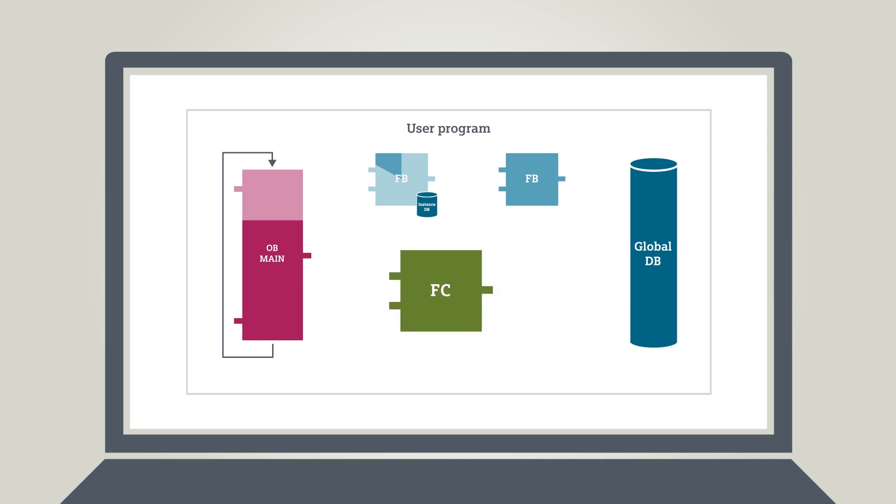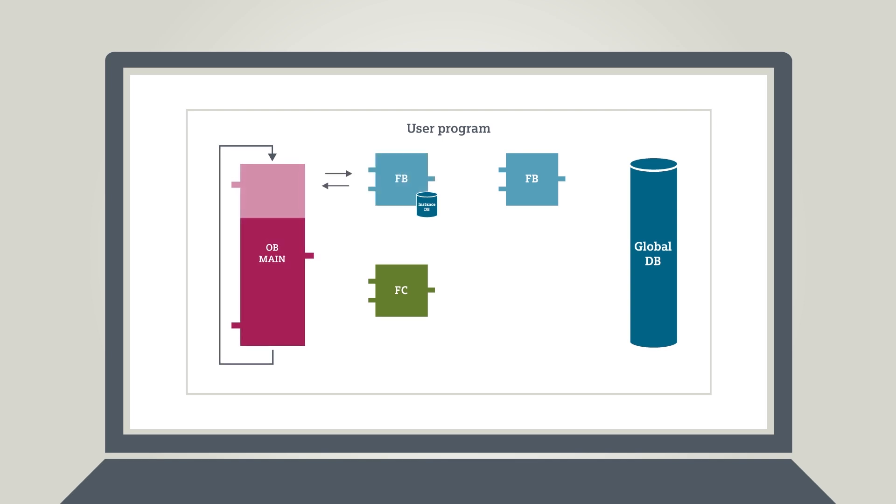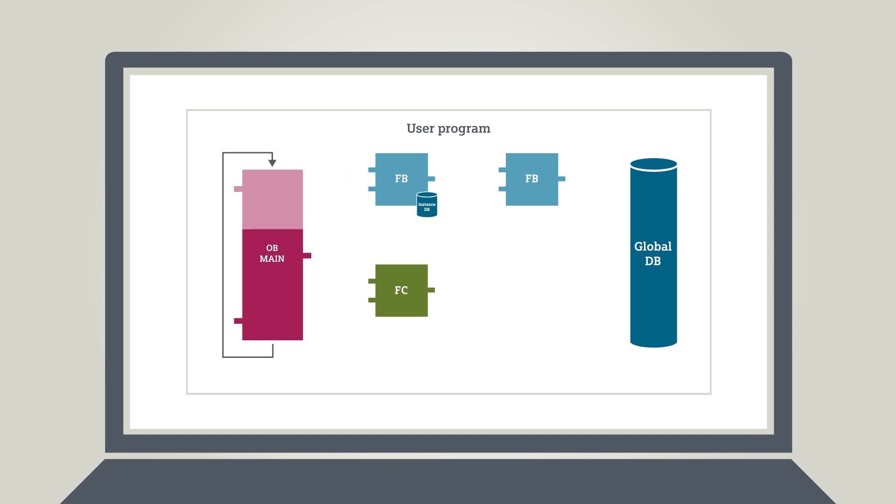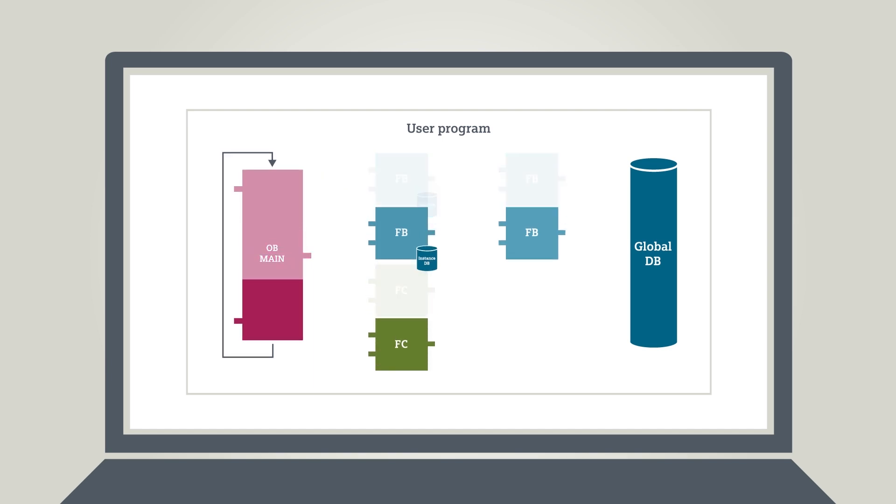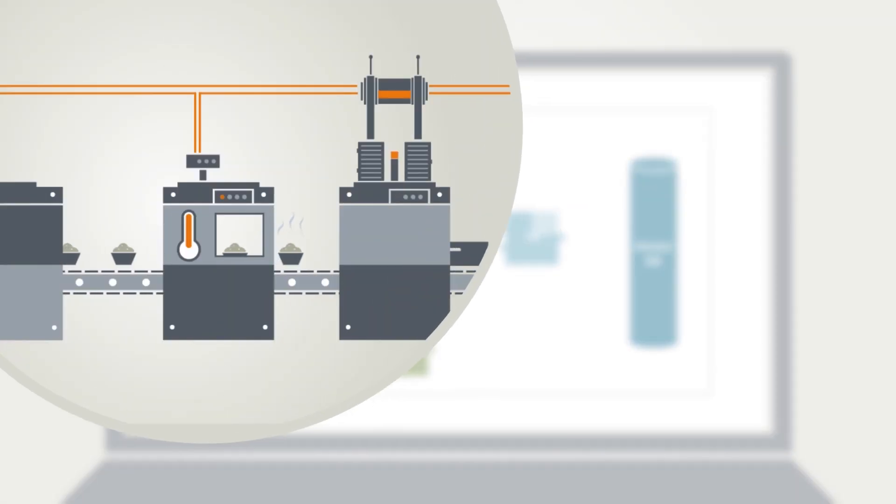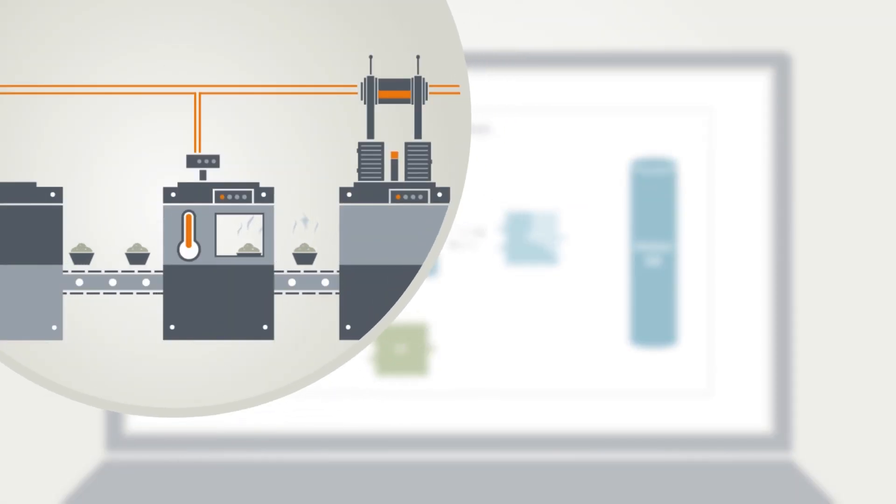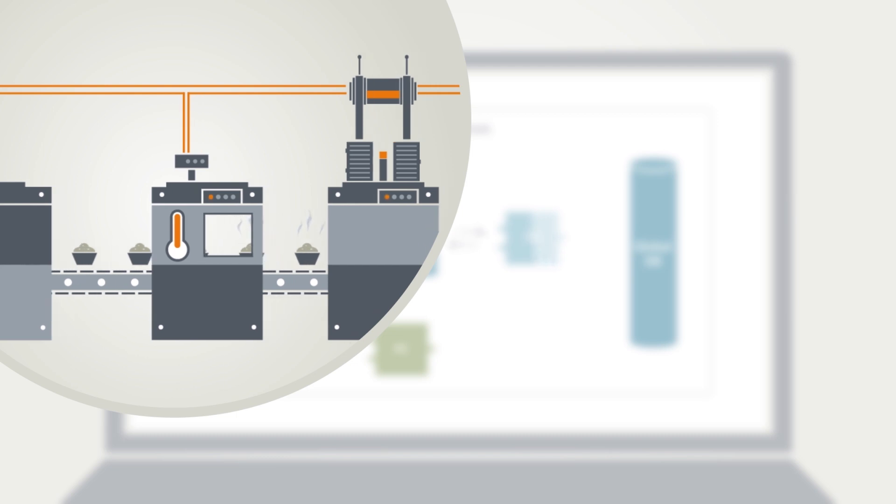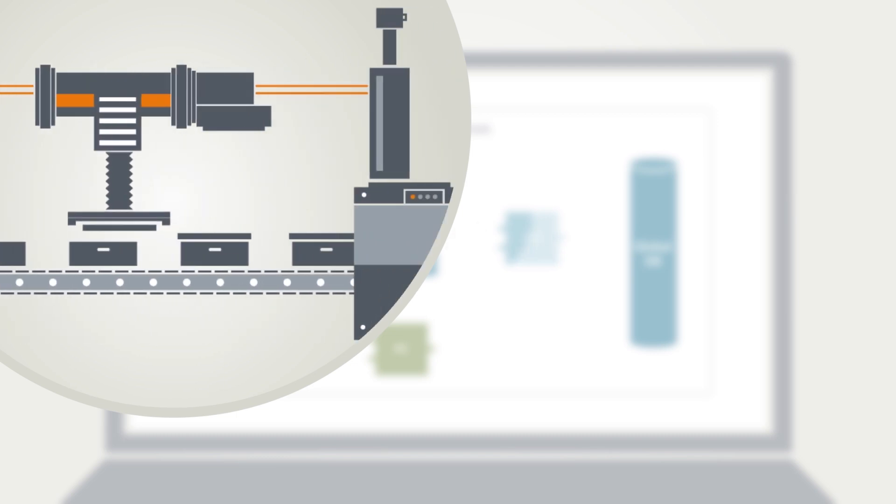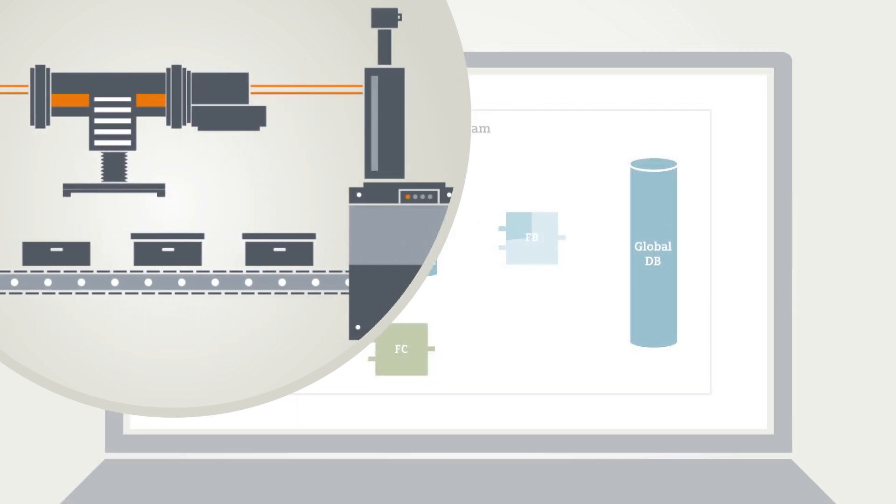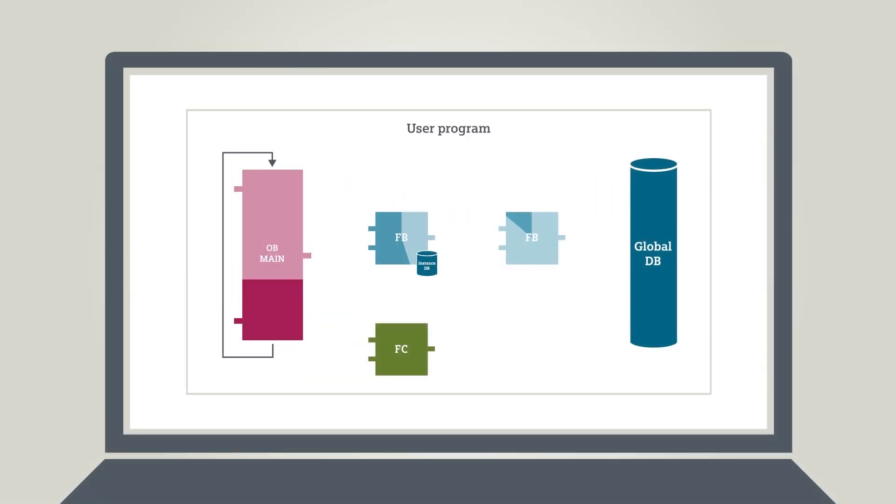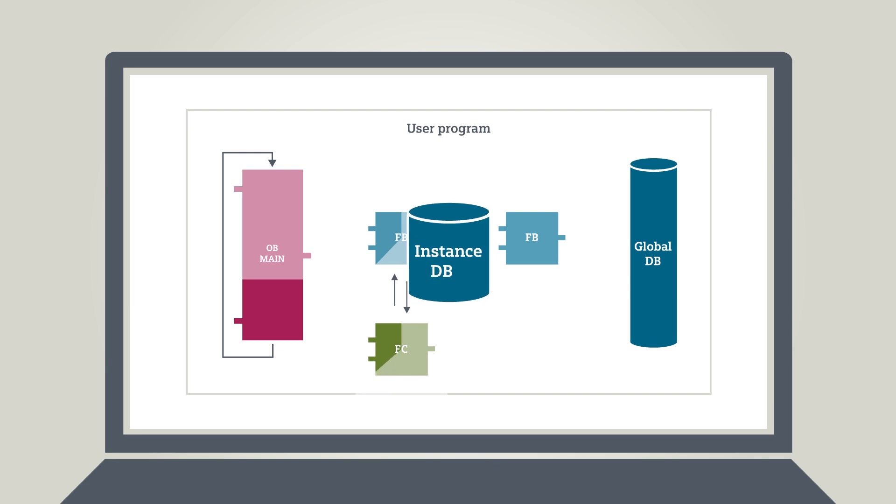Once the program of the first conveyor belt has run its course, it will jump back to the return address of the block from where it was called up. One by one, all other components required for the system run will be called up in sequence. Identical system components, such as an identical conveyor belt, can now be processed by simply calling up the same block, but with different parameters and individual instance DBs.